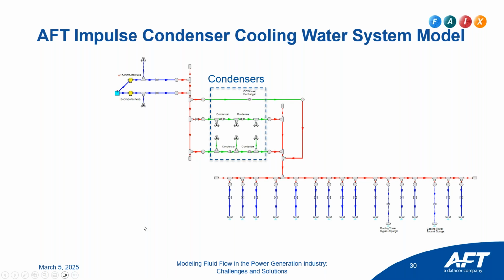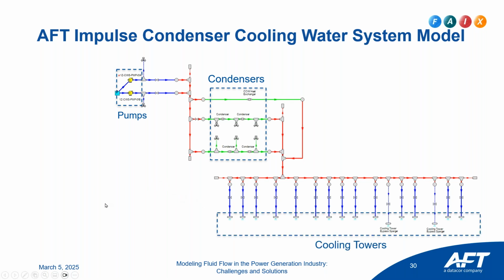Okay, the two pumps that provided the 158,000 GPM of flow, vertical turbine pumps, were over here on the left, and those were, anybody in here, any fans of Flowserve? They were Flowserve pumps. And then the cooling towers were all down here, cooling tower discharges down here. And then this is a 99% closed loop system because the cooling tower cooled water would then feed back into the basins and then feed these pumps again.